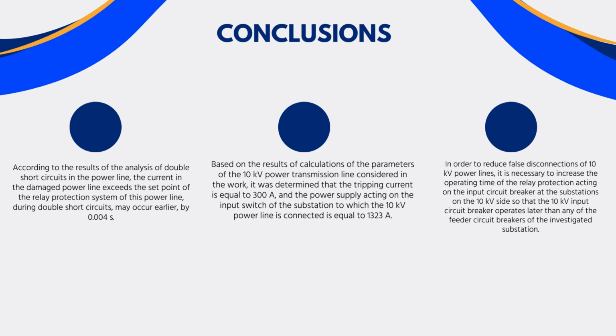So, based on the result of calculation of the parameters of the 10 kV power transmission lines considered in the work, it is determined that the tripping current is equal to 300 amperes, and the power supply action on the input switch on the substation to which the 10 kilovolt power line is connected is equal to 1323 amperes. So the obtained model can help us to recalculate similar schemes and gives us the possibility to design our grid taking into account high penetration renewable energy sources.